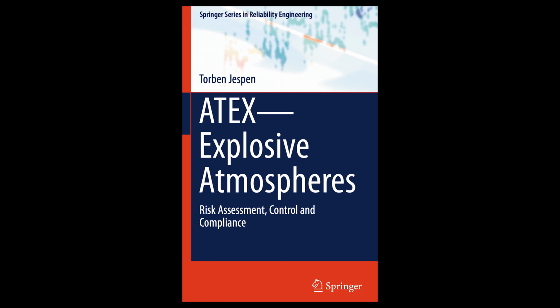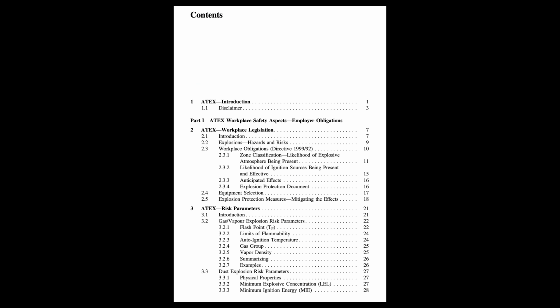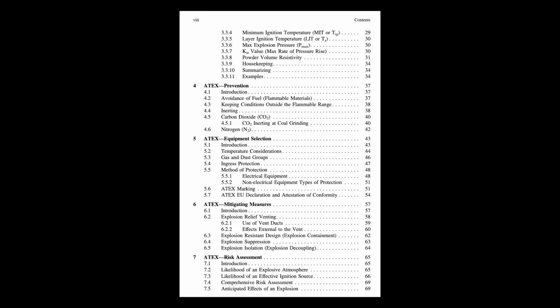The guide also makes the point that non-electrical equipment, mechanical gear, also needs assessment, often involving an ignition hazard assessment, or IHA, to determine its category and if specific protection methods are needed. And IP ratings, ingress protection, how critical are they, especially for dust? Very critical for dust. The IP rating tells you how well sealed the enclosure is. IP6X means fully dust tight. No dust ingress permitted. IP5X means dust protected.